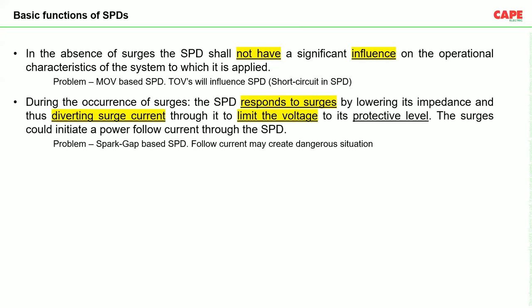Second basic function of SPD is, during the occurrence of surges, the SPD shall respond to the surges by lowering its impedance and thus diverting the surge current through it to limit the voltage to its protective level. The surges could initiate a power follow current through the SPD. That means once there is a surge, SPD should immediately respond by doing two things. First, it has to create an equipotential. It has to limit the voltage to its voltage protection level. Second, it has to divert the surge current to earth or source wherever it is applicable.